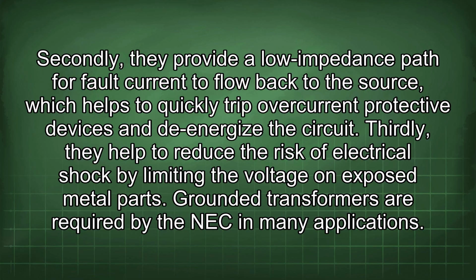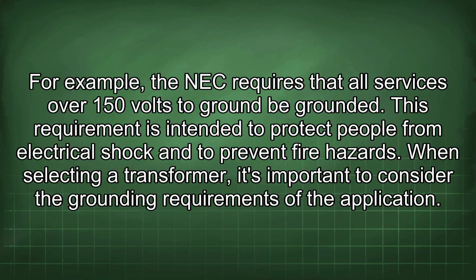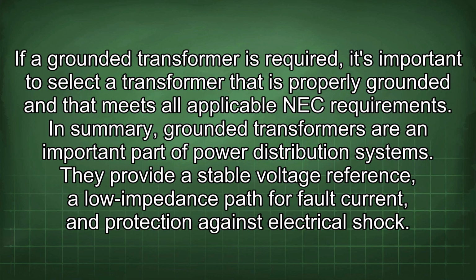Grounded transformers are required by the NEC in many applications. For example, the NEC requires that all services over 150 volts to ground be grounded. This requirement is intended to protect people from electrical shock and to prevent fire hazards. When selecting a transformer, it's important to consider the grounding requirements of the application.